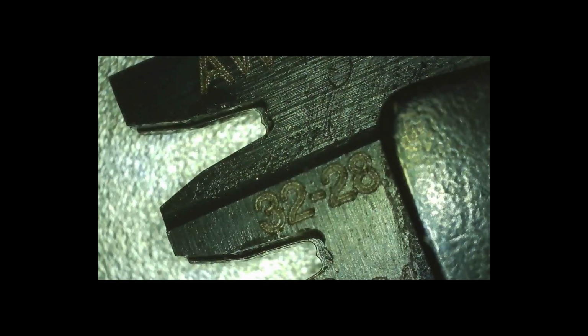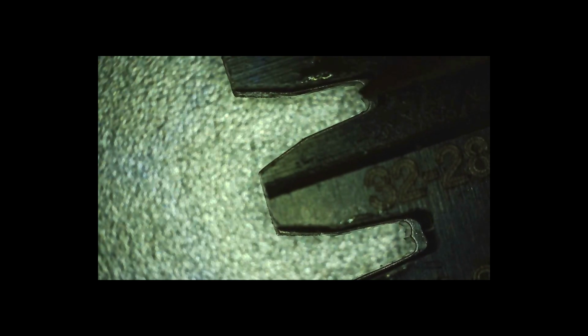All right, so hopefully... Okay, actually, these are basically dies. It's called a die pair. So let's bring one of them in. 32 to 28 AWG. That's more likely what we'll be using. I don't know if you can see, but it's kind of stepped. Essentially, you'll be feeding the wire in from this side. You'll be cradling the connector into here. That's tricky to get set up. And then with that step, you'll push the wire through and use the step to hold the insulation, and that'll set your depth gauge basically. That way you're not pushing your insulation too far in, because if you go into that center part, you're going to wrap around insulation and not even grab hold of the conductor, and it's not going to work.